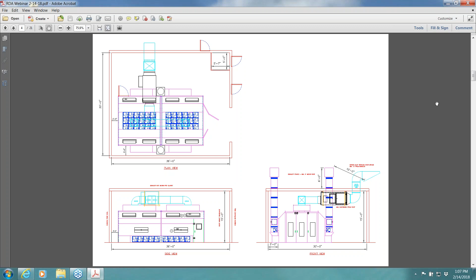Codes: when it comes to codes, the main governing code for construction of a paint booth is NFPA 33, Standard for Spray Application Using Flammable or Combustible Materials, and the latest edition of that is 2016. That's what tells you what type of metal it's got to have in order to build a booth—if it's single wall, it's got to be 18 gauge; if it's double wall, you can use 2 sheets of 20 gauge, things like that.